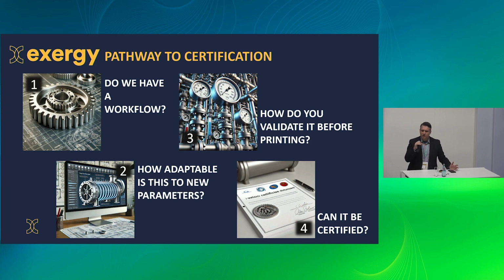They also raised 4 key questions we had to address. First, can we develop a straightforward workflow to design a heat exchanger that meets specific requirements, like a specific heat capacity or pressure drop? Then, is this adaptable? If we need one small change, do we have to start from scratch? Next, can it handle the pressures we're asking it to handle, and can we validate that performance before it's printed, since printing is really expensive? And then, how can we get it certified? We have our local regulatory body in Alberta, the Alberta Boiler Safety Association, or ABSA. So how do we get it to them, and how do we get them to accept it?